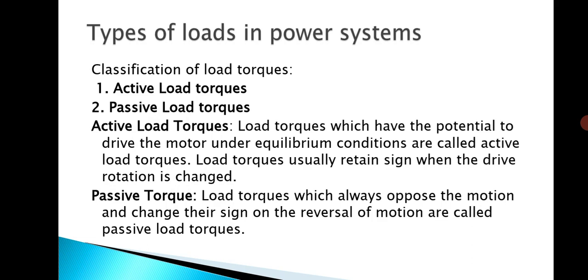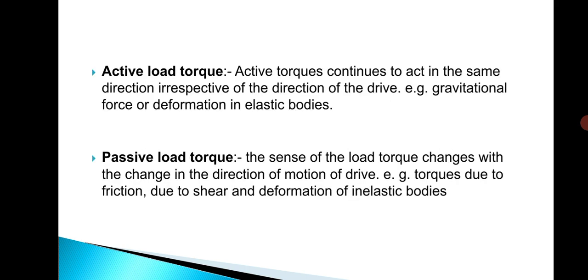Passive load torques always oppose the motion and change their sign on reversal of the motion — these are called passive load torques. For example, if a motor is being driven and due to friction the direction of the motor may change, this type of load torque is called passive load torque. Active load torques continue to act in the same direction irrespective of the direction of the drive, such as gravitational force or deformation in an elastic body.